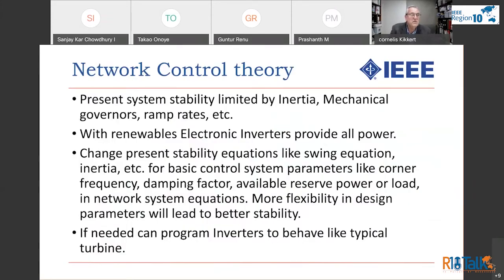So if we look at network control theory, the present system stability is limited by inertia, mechanical governors, ramp rates, and so on. With renewables, electronic inverters provide all the power, with very different stability criteria. So we need to change the stability equations, like the swing equation, inertia as a basis for control, and we use parameters like corner frequency and damping factor, the standard sort of classical control theory. And we need to have available reserve power or load, because that's much more flexibility, we're no longer constrained to the mechanical parameters. We will be able to get much better stability. If needed, we can program inverters to behave like a typical turbine, but that's not the best way of doing things.